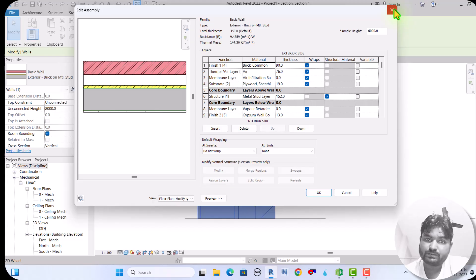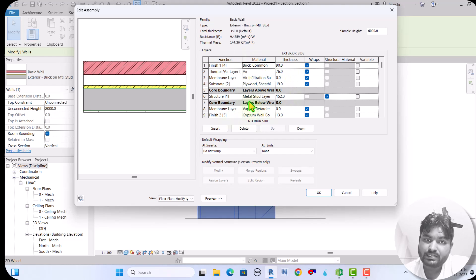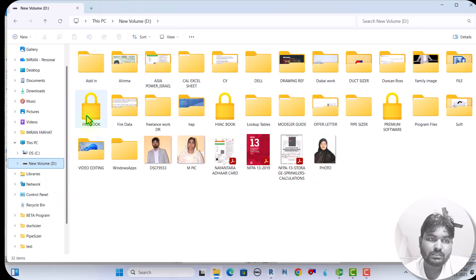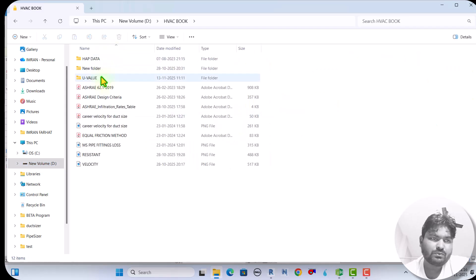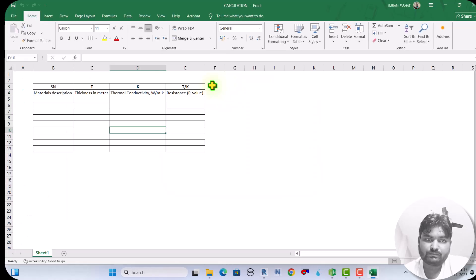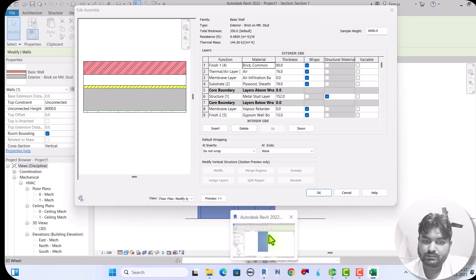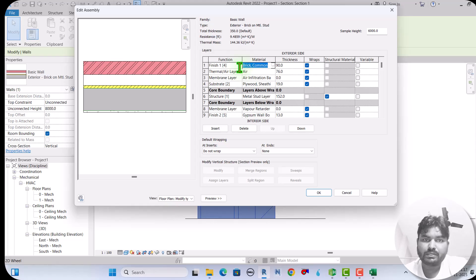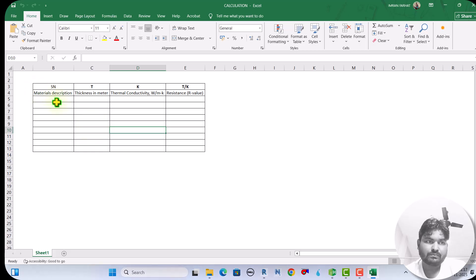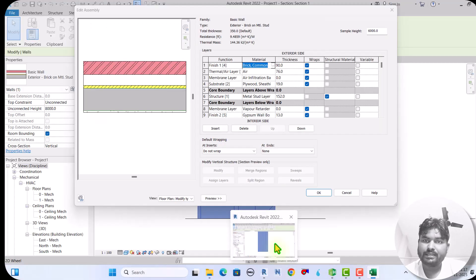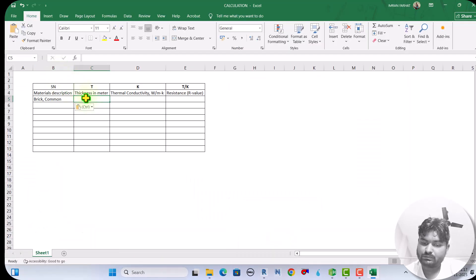To get the thermal conductivity values, I reference a standard table — specifically the CIBSE guide. The thermal conductivity of each material, such as brick with thickness 90 mm (0.090 m), is found in this table. Let me look up the values one by one.